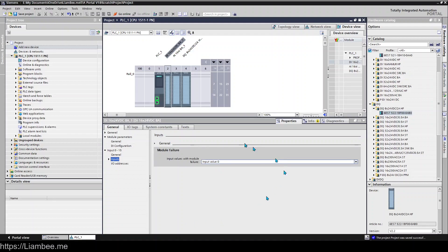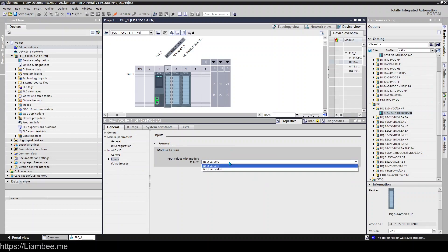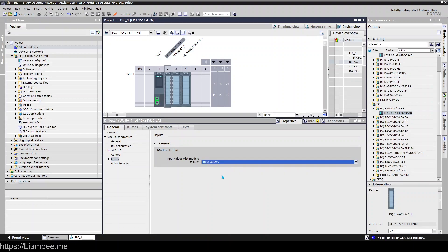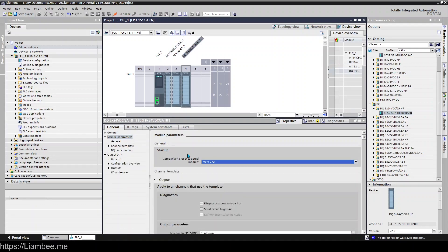What do you do when this module fails? So you can either keep the last known value or set your input value as false. If we have a look at the configuration for outputs, there's a little bit more going on in terms of what you can set.